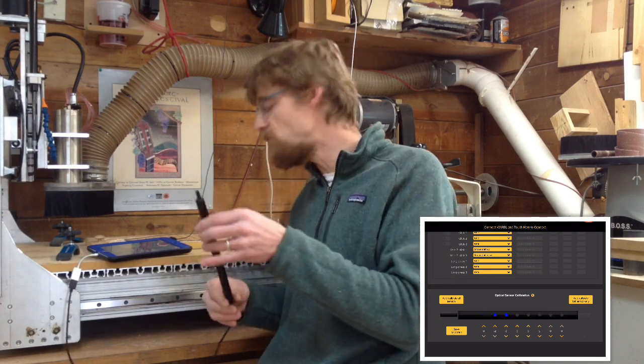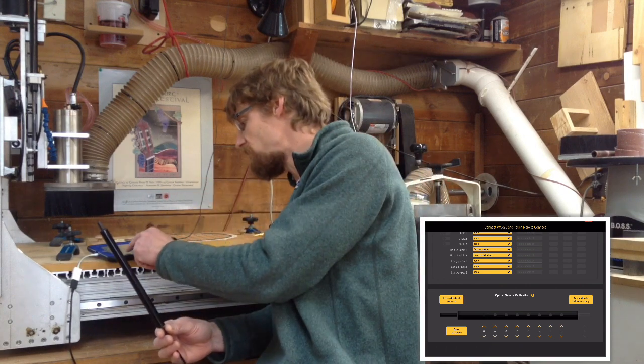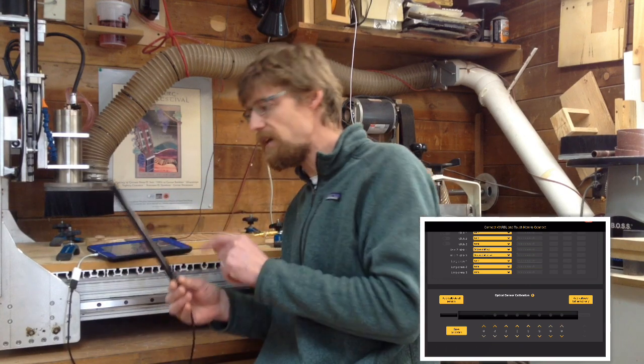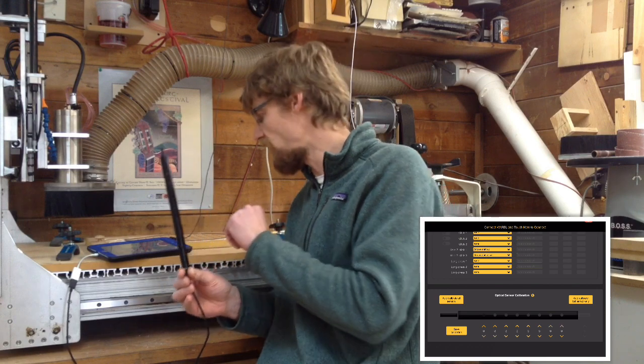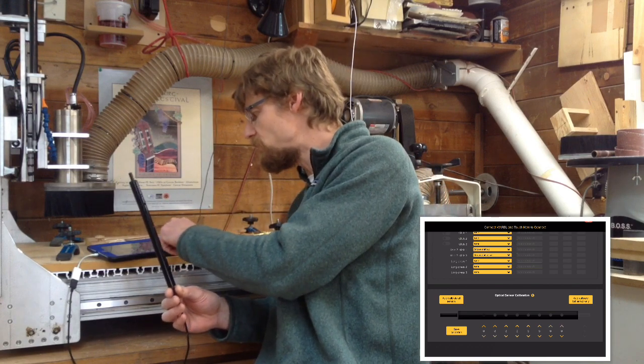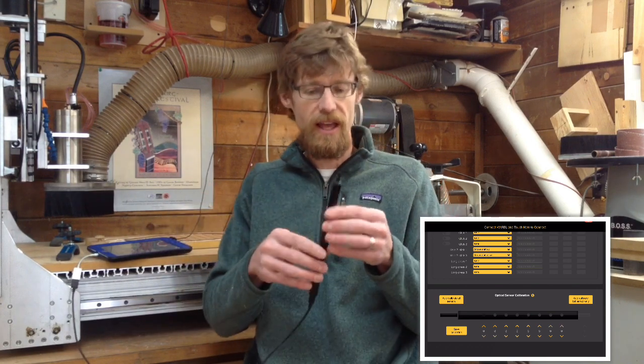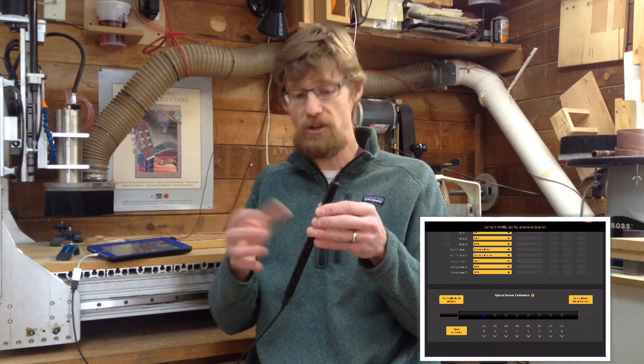So at that point, you do need to click Save Calibration to save those adjustments. So if I do that, the LED in the back of the device flashes 3 times. All the little numbers between the arrows reset to 0. And it's at that point you're done fine-tuning it.